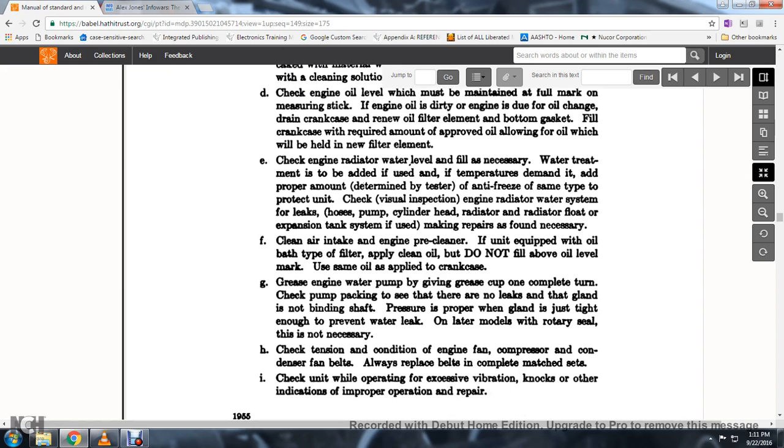f. Use the same oil applied to the crankcase. Grease the engine water pump; give the grease cup one complete turn. Check the pump packing to see that there are no leaks at the gland.